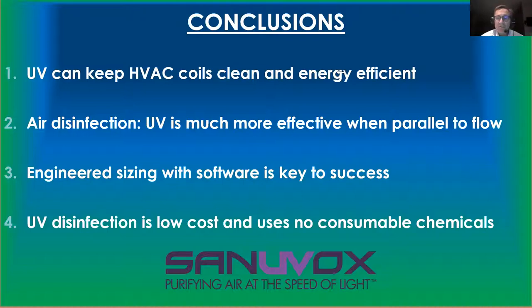On the immediate surface where the lamps are installed, there's never a problem, but it's inside, with the multiple reflection inside of the UV. Although aluminum is a good reflector, you lose some by multiple reflection. So to work your way through the coil and make sure you disinfect down to the opposite side, that's why we need that criteria of 1 hour. If we try to do it at 24 hours, by the time you're finished, there will be some more growth on the opposite side of the coil.